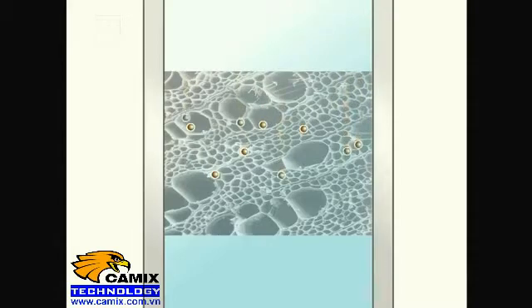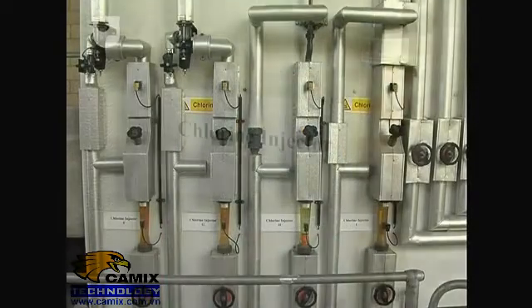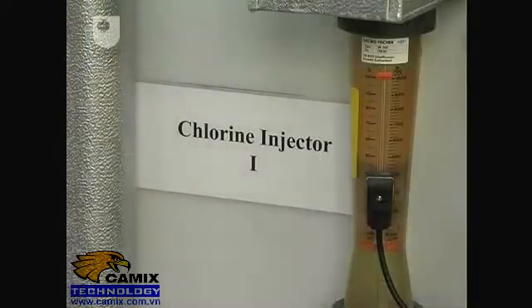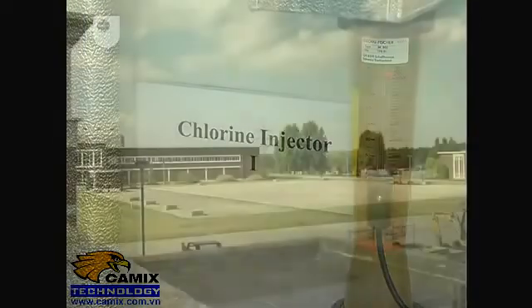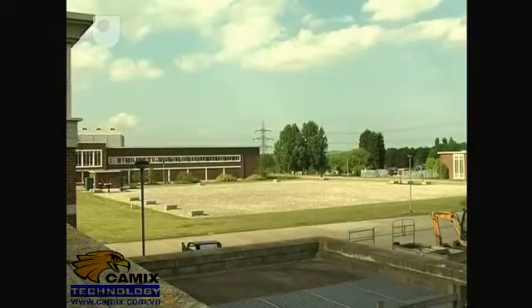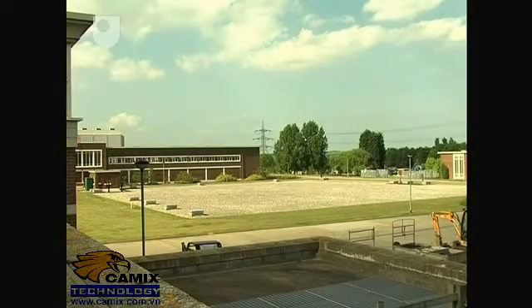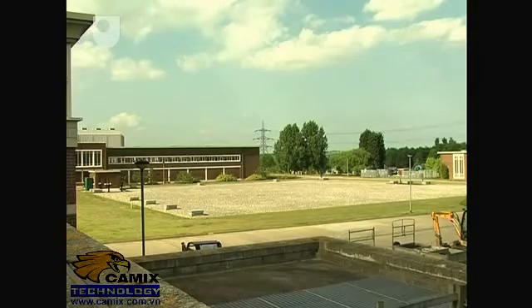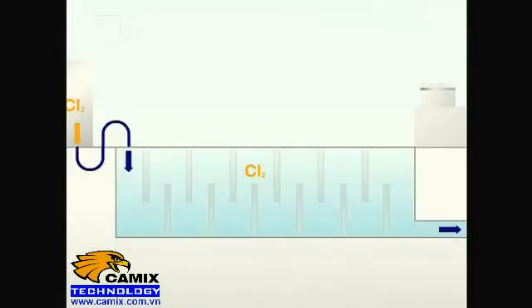By now, the water is very clean, and the process is almost complete. Chlorine is added to kill any remaining pathogenic bacteria present. And the final step occurs underground in a contact tank. Here the water is held for a carefully calculated residence time of about four hours to allow the chlorine to take effect.